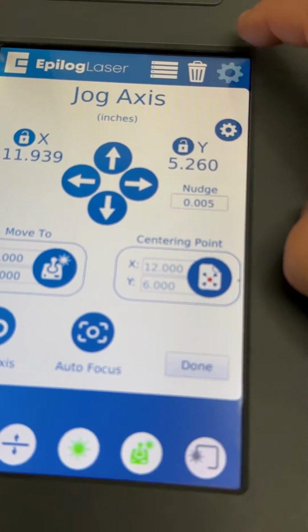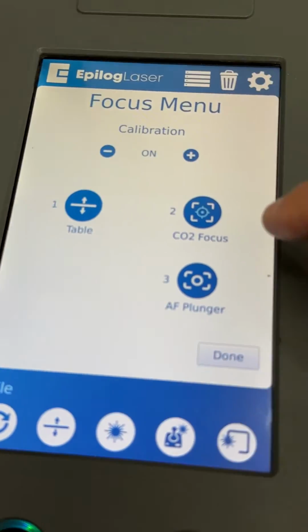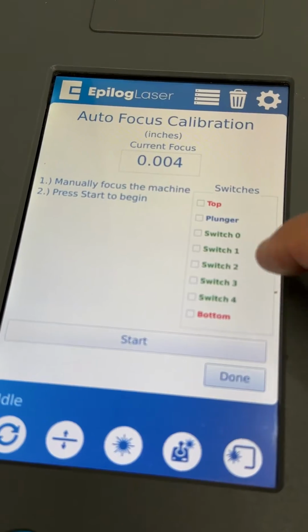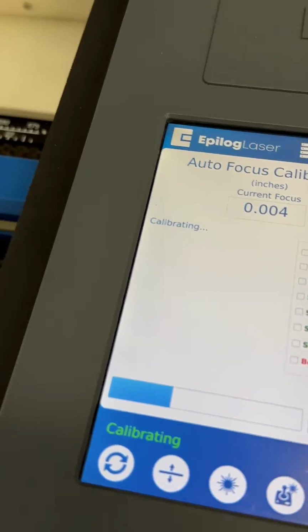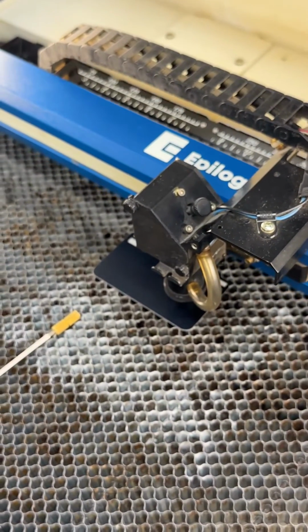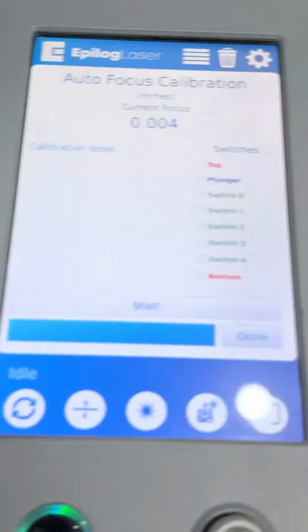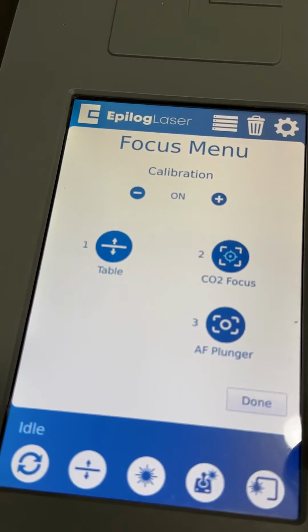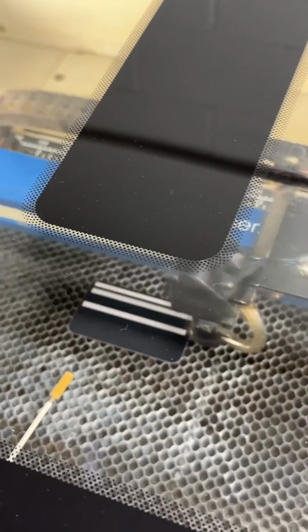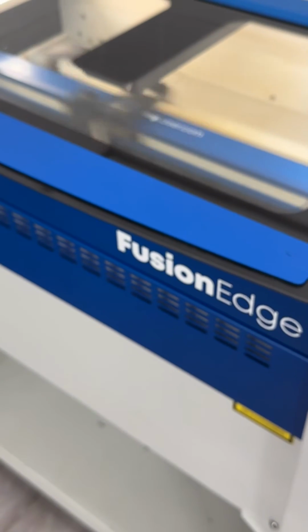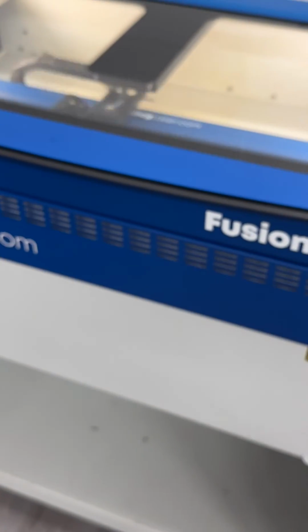And then we're going to go back to gear, focus, and auto plunger. And this is going to say start. And now our autofocus has been correctly set. And so that's how you calibrate the Fusion Maker, Edge, and Pro, the autofocus calibration.